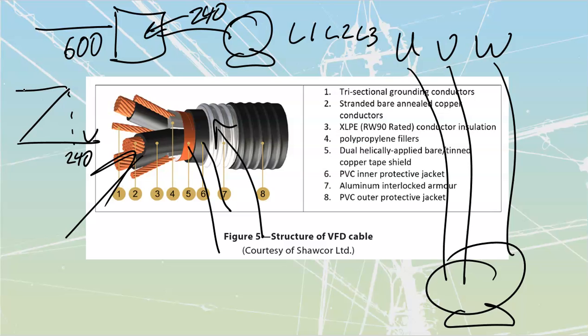They're big caps, and they're going to take a good 5 minutes before they're completely discharged. One of the worst things you can do is just shut off power to the VFD and go poking around there immediately, because you've still got a lot of voltage on the DC bus. And if you accidentally contact that DC bus, it's going to hurt. DC hurts way, way worse than AC ever will.